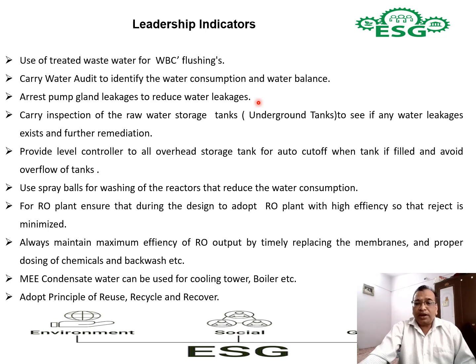So you have to see that gland packing and preventive maintenance are arrested. Then carry out inspection of raw water storage tanks, particularly the underground tanks, to see if any water leakages exist, and do further remediation. Most of the time the underground water tanks are old. Maybe there are seepages through the civil work. So you have to identify this and immediately do the remediation measures.